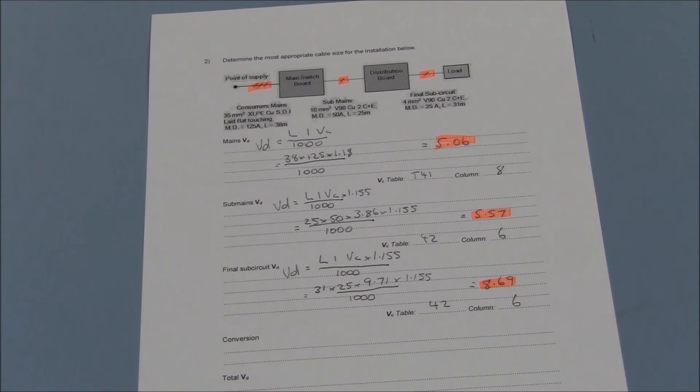Finally, the single phase drop of the final sub circuit is 8.69. Again, remember to multiply the value of VC by 1.155 as it's a single phase circuit. Table 42 column 6 is the reference once more.